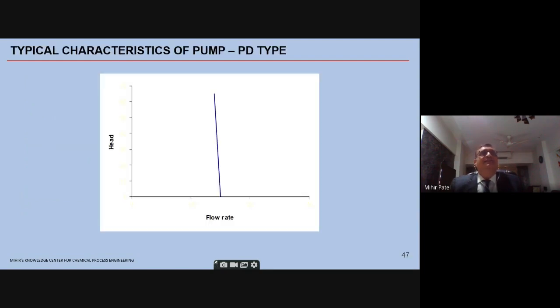Now, typical characteristic of PD pump. As I mentioned earlier, flow rate and head is a very vertical line, because the positive displacement pump always operates against the back pressures. That's why in the PD pump data sheet, discharge pressure is always mentioned. You don't mention differential head like for a centrifugal pump.